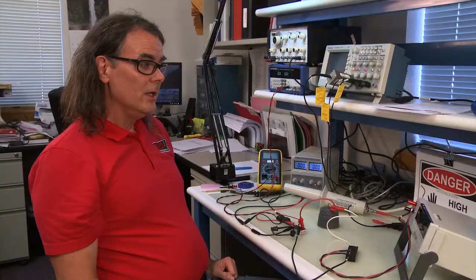In addition, I wanted to demonstrate using a high voltage oscilloscope probe. So this is a typical high voltage oscilloscope probe. I've already got it connected to the scope through its input module here, and I connect the ground lead of the high voltage probe to my ground bus here, and then I connect the positive lead of the high voltage probe to my high voltage standoff. So that's my second monitoring device there.